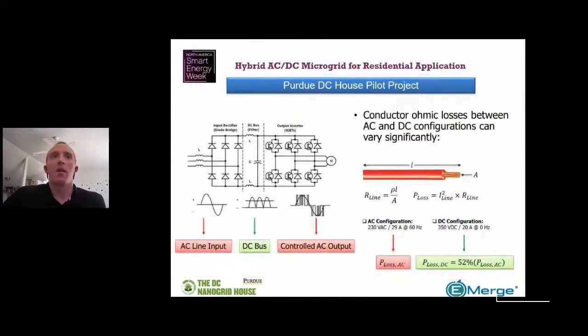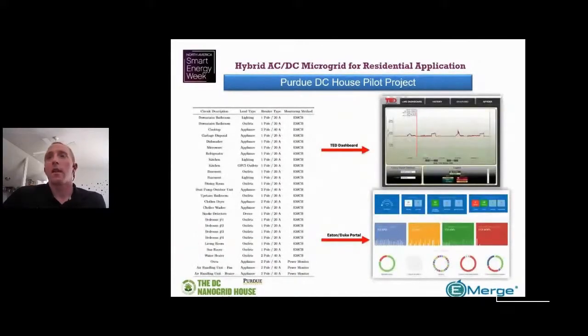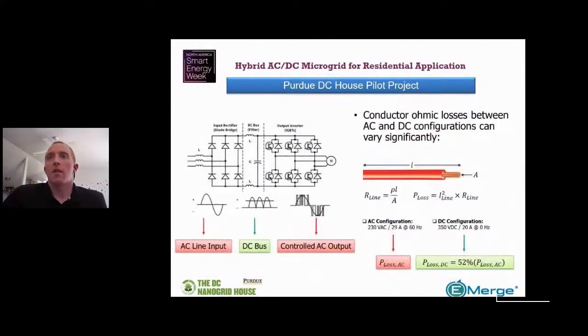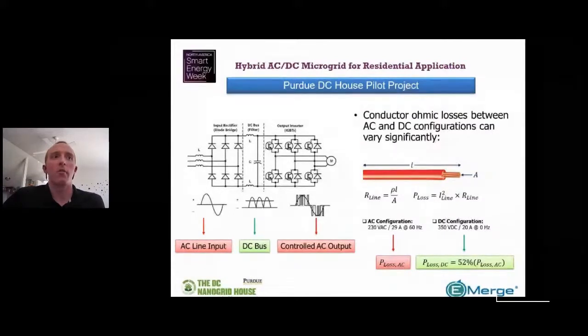With that in mind, looking at the types of equipment we can retrofit to see a real benefit from running a DC grid — the first thing we looked at is a heat pump. In the US, heating and cooling alone can run about 50% of your energy costs throughout the year. On the left side of this slide you see a typical conversion from an AC input to a controlled AC output that would run a motor in a heat pump type device.